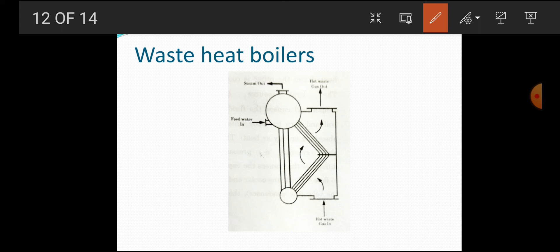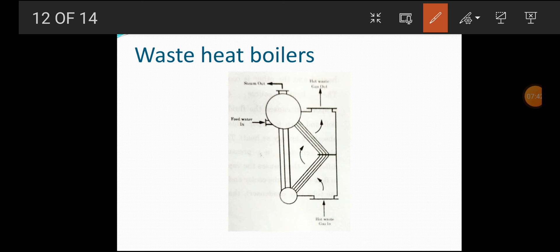Waste heat boilers generally operate using exhaust gases from turbines, reciprocating engines, and furnaces in the medium temperature range. Waste heat boilers are water-tube boilers in which exhaust gases are allowed to pass over a number of parallel water tubes. Due to the exhaust gases passing over the water tubes, the water gets evaporated and saturated steam is produced. This steam is collected in a steam drum and used as process steam.